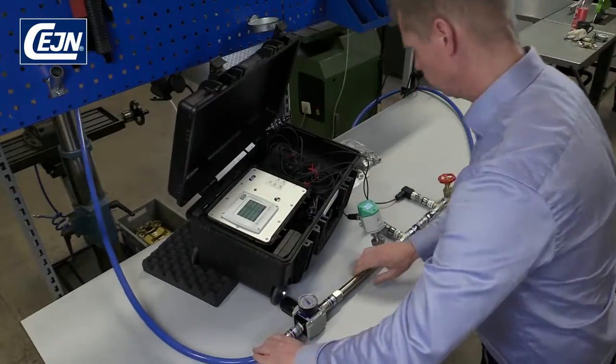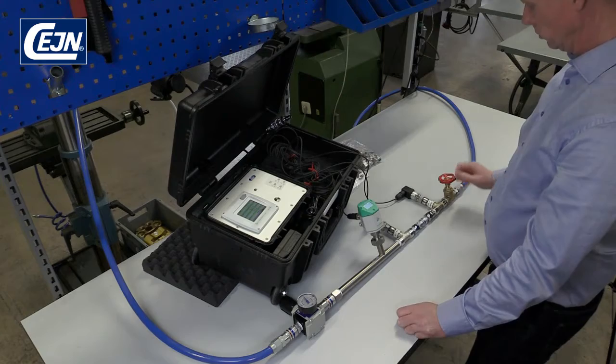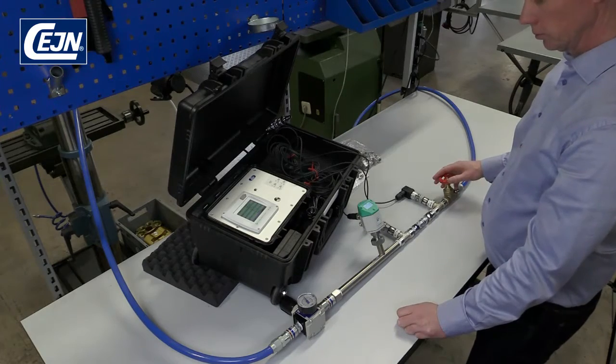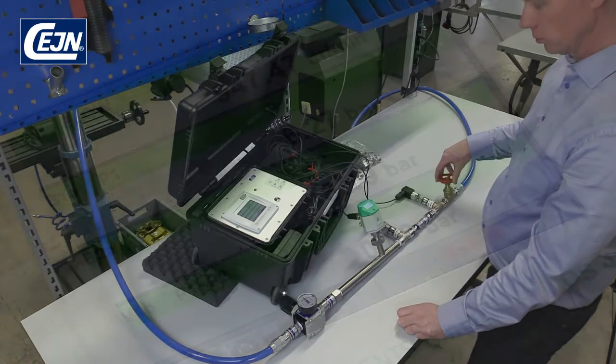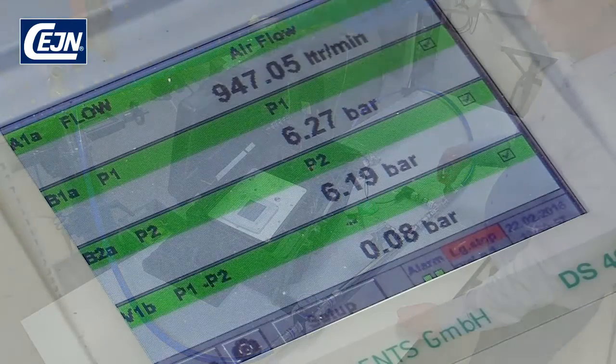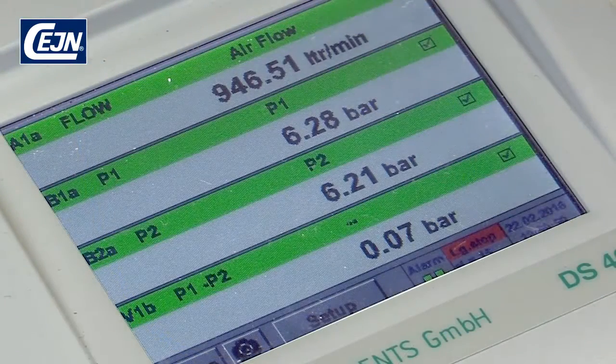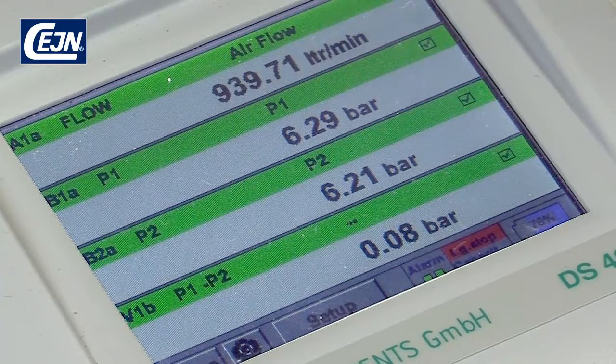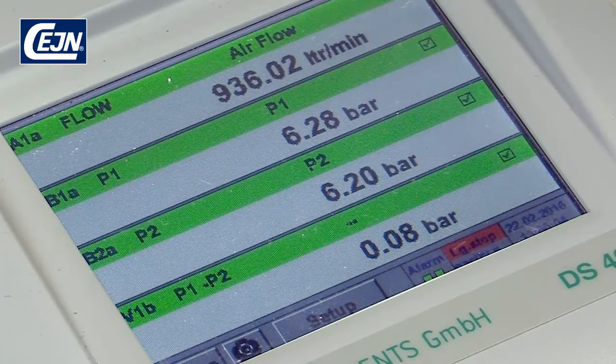When you connect the hose, check that the pressure is not over 10 bar. Normally the pressure is around 6 to 7 bar. Use the valve to adjust how many litres you want to flow through. In this case, we want it to be around 900 litres.